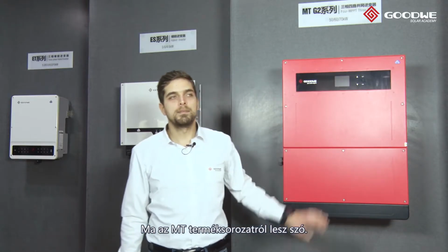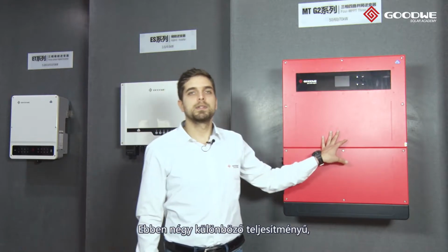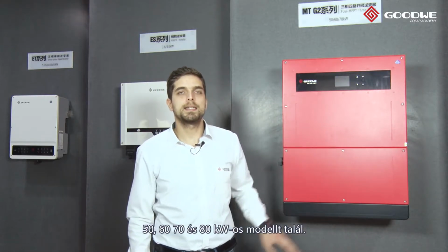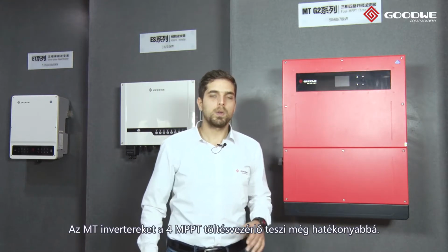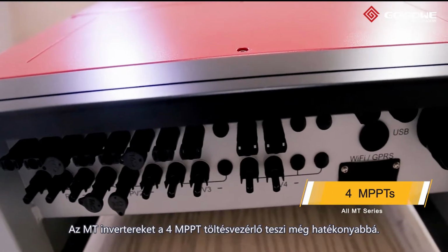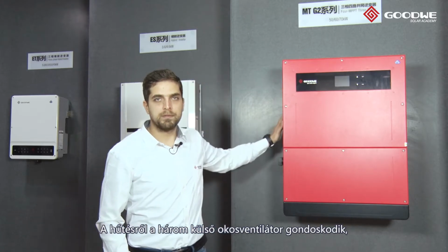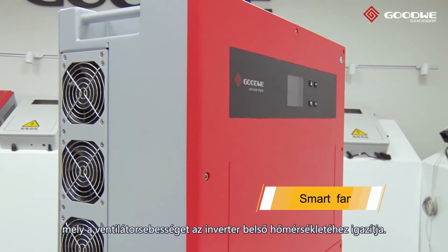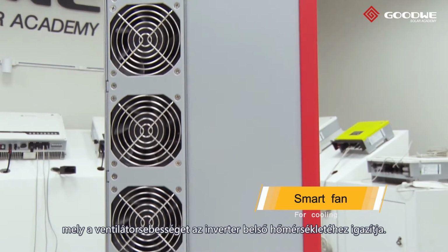Today, we will focus on MT series. Here we have four different capacities, which are 50, 60, 70 and 80 kilowatts. All MT series have 4 MPPTs that allow you to get more efficiency. For cooling, there are 3 external smart fans. They adjust the speed of the fan in accordance with the inside temperature of the inverter.